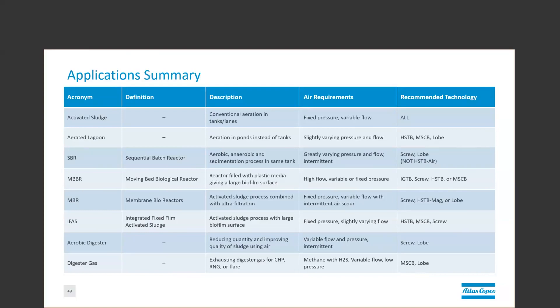The MBR, or membrane bioreactor, is typically a fixed pressure application with variable flow, and then typically an intermittent air scour application to clean the reactor itself. Here, the rotary screw, magnetic bearing high-speed turbo, or rotary lobe are typically a good fit. The IFAS, or integrated fixed film activated sludge process, is typically a fixed pressure varying flow application. So a high-speed turbo, multistage centrifugal, or screw tend to be a good fit.